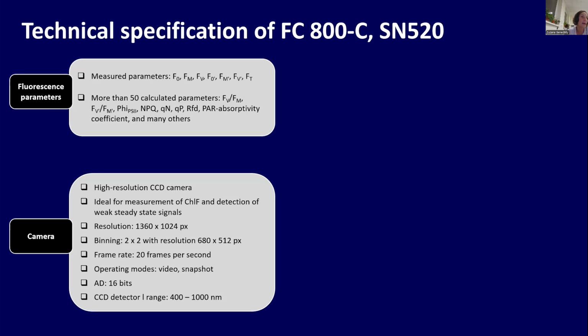The camera is quite fast. It can take 20 images per second. I already mentioned it can operate in video mode. This is a mode that you will use mostly, but it can be switched to another mode called snapshot. This is a mode that we use for long integration times. The AD converter is 16 bits. So the signal that you measure from the camera is in a range between 0 and approximately 60,000 gray levels. And the detector is sensitive in the whole visible spectrum. This CCD chip is silicon, so it's sensitive up to 1000 nanometers.